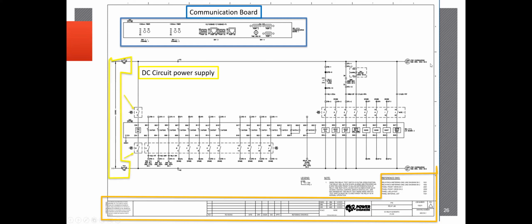So we got that. Your DC circuit power supply. This is extremely important when you're first looking at the prints, because you want to identify what breaker in the control house is associated with the relay, because it's pretty crucial for making sure that it's powered up when it needs to be, verifying that it's getting proper voltage to the relay, because you don't want to fry the relay. I mean, the things are a couple thousand, $10,000 most of the time. So damaging one of those probably wouldn't impress the client too much.